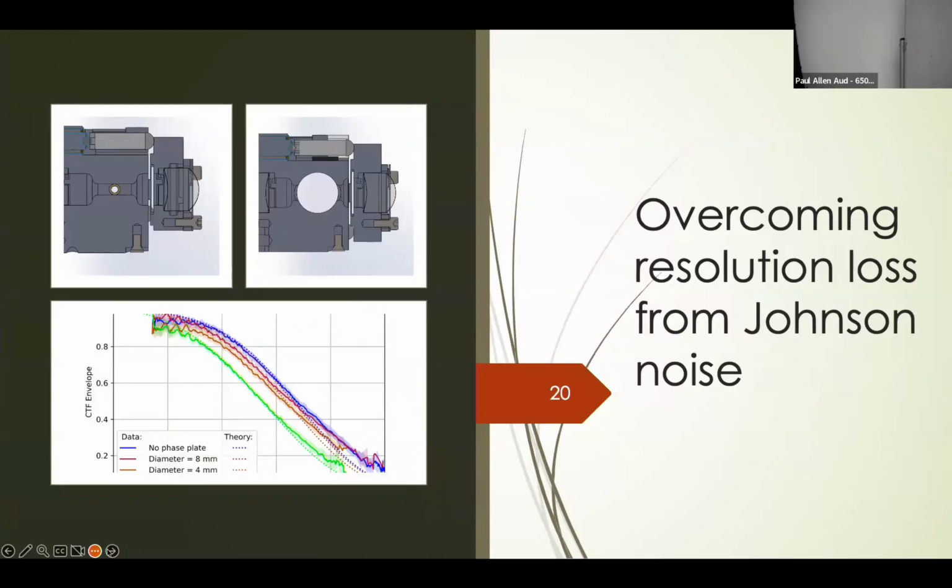First, because of the extra magnification of our extra electron lenses. And second, because the beam hole in the cavity was very narrow, and that means that the beam has to go very close to these metal walls. So the fix was in principle easy, but took several months for the machine shop to manufacture a cavity with a much larger hole. And when we had that, we could show that the contrast transfer function, which tells you essentially everything you need to know about the resolution of your microscope, is virtually indistinguishable between having no cavity and having the cavity with a large hole.